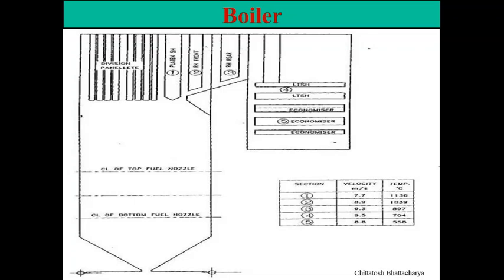They are placed at the second pass. These are part of the primary superheaters. Then from there it is going to the platen superheaters. From there to the final superheaters. Final superheaters are placed in the joining of the radiant and convective zones, and subsequently steam is sent to the turbine, HP turbine, as superheated steam, final superheated steam.